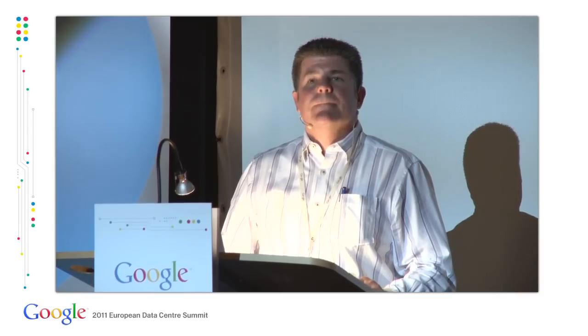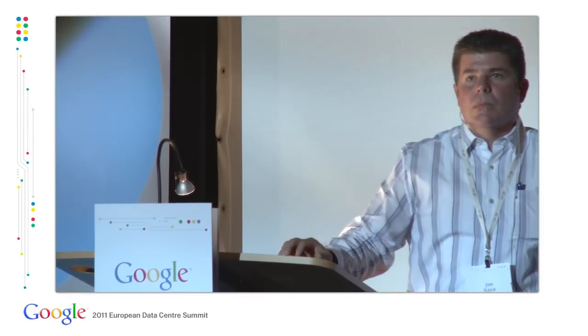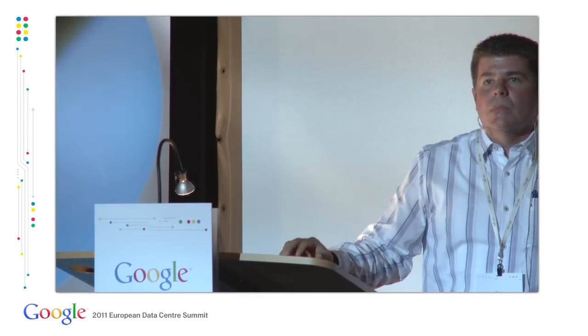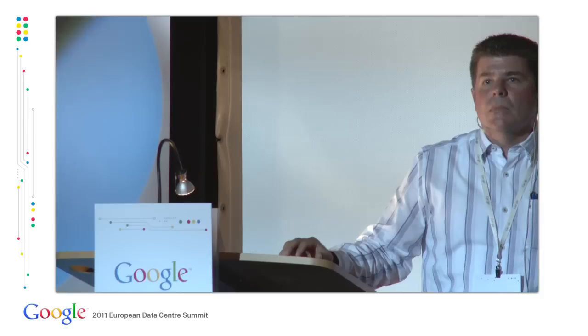Okay. My question had a secret meaning, didn't it? And I didn't make it clear. In the fully allowable or permissible range of 20 to 80, in the same document there's actually a warning about going above 60% RH for long periods of time because it damages the hardware. I just wondered what your room actually settled down to. Above 60% RH is quite humid anyway, but you don't know what it actually settled down to. I don't have that data at the top of my head.